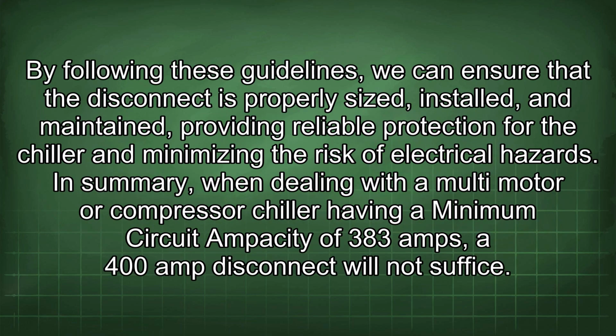By following these guidelines, we can ensure that the disconnect is properly sized, installed, and maintained, providing reliable protection for the chiller and minimizing the risk of electrical hazards. In summary, when dealing with a multi-motor or compressor chiller having a minimum circuit ampacity of 383 amps, a 400 amp disconnect will not suffice.